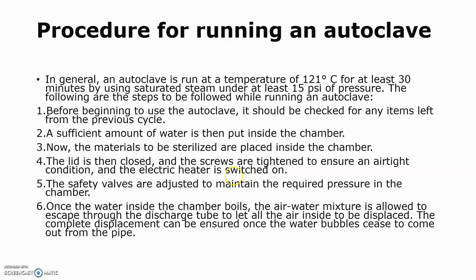Before running the autoclave, we should check for any items left from the previous cycle. A sufficient amount of water should be put inside the chamber. Now we should place the materials to be sterilized inside the chamber. Then we close the lid and the screws are tightened to make it airtight, and then we switch on the electrical heater. Then we adjust the safety valves to maintain the required pressure. Once the water inside the chamber starts boiling, the air-water mixture is allowed to escape through the discharge tube to let all the air inside be displaced. The complete displacement can be ensured once the water bubbles stop coming out from the pipe.